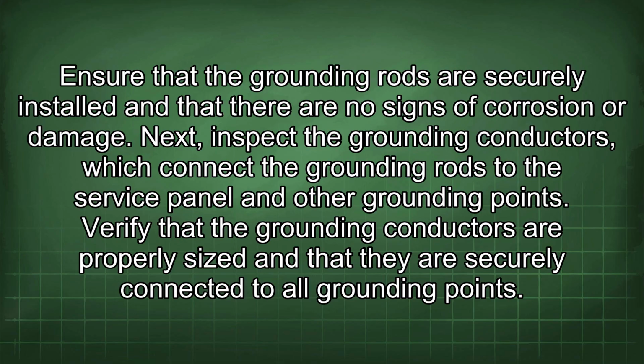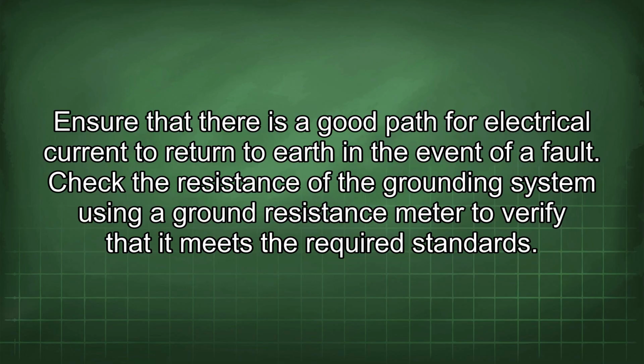Next, inspect the grounding conductors, which connect the grounding rods to the service panel and other grounding points. Verify that the grounding conductors are properly sized and that they are securely connected to all grounding points. Ensure that there is a good path for electrical current to return to earth in the event of a fault. Check the resistance of the grounding system using a ground resistance meter to verify that it meets the required standards.